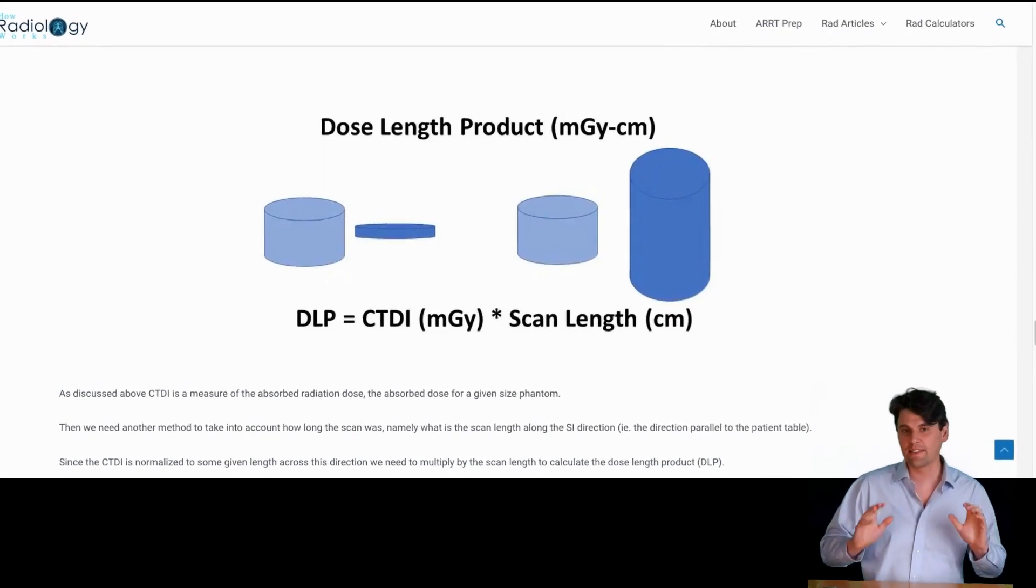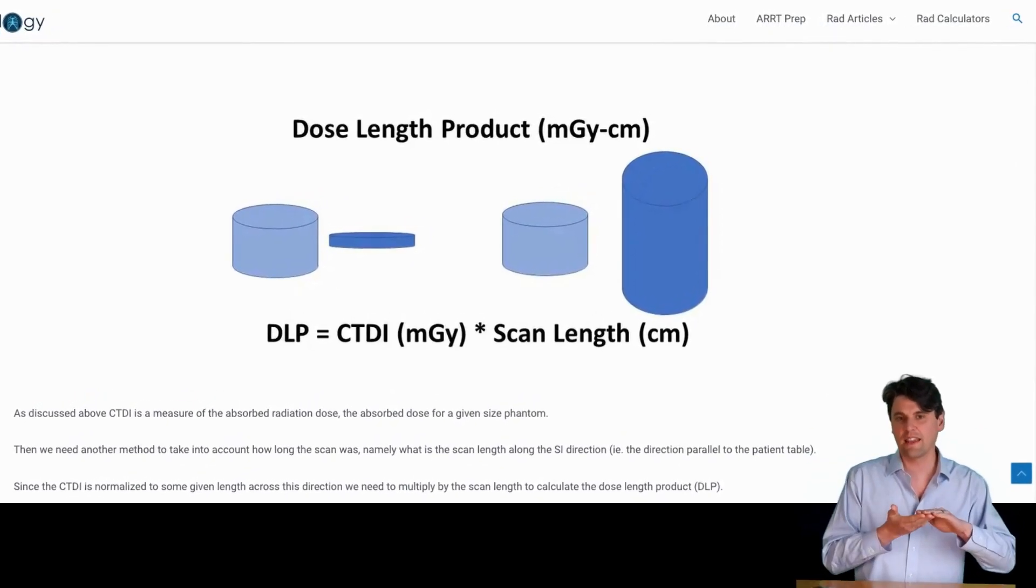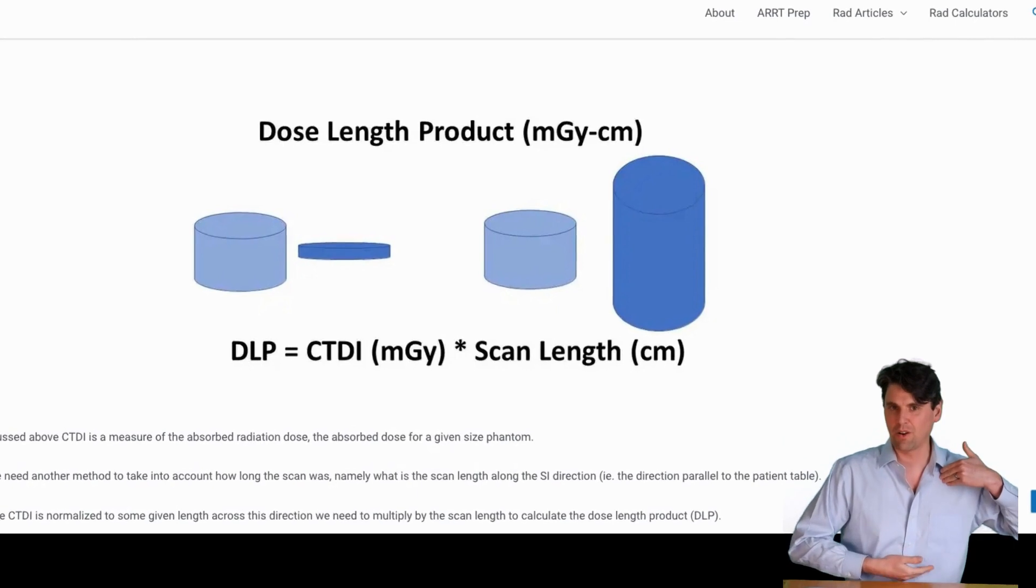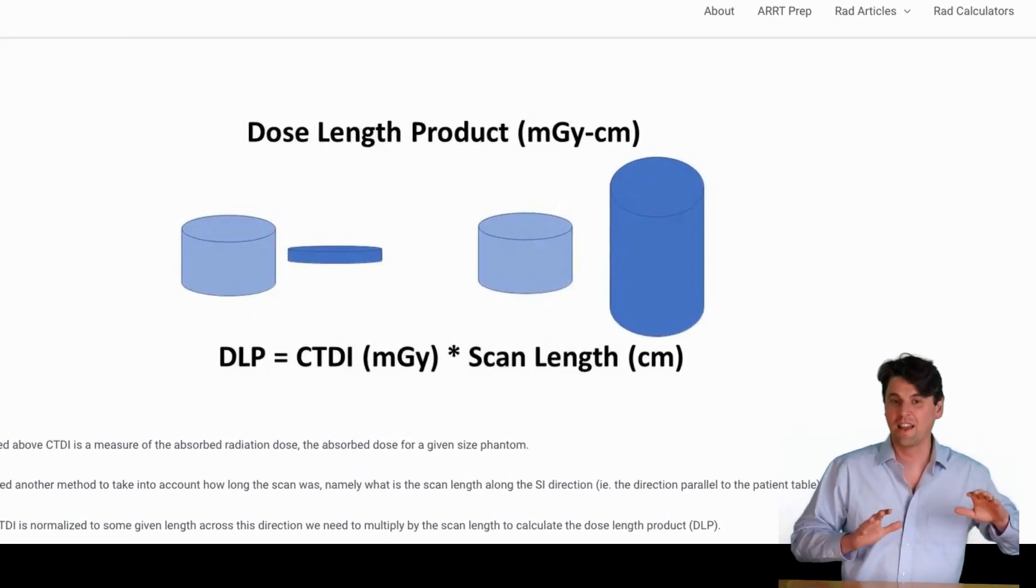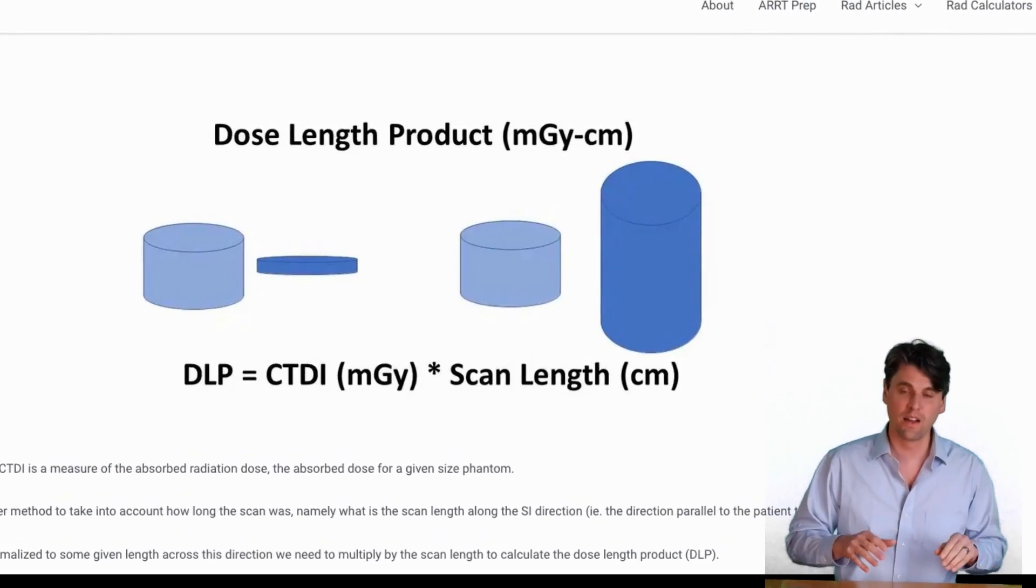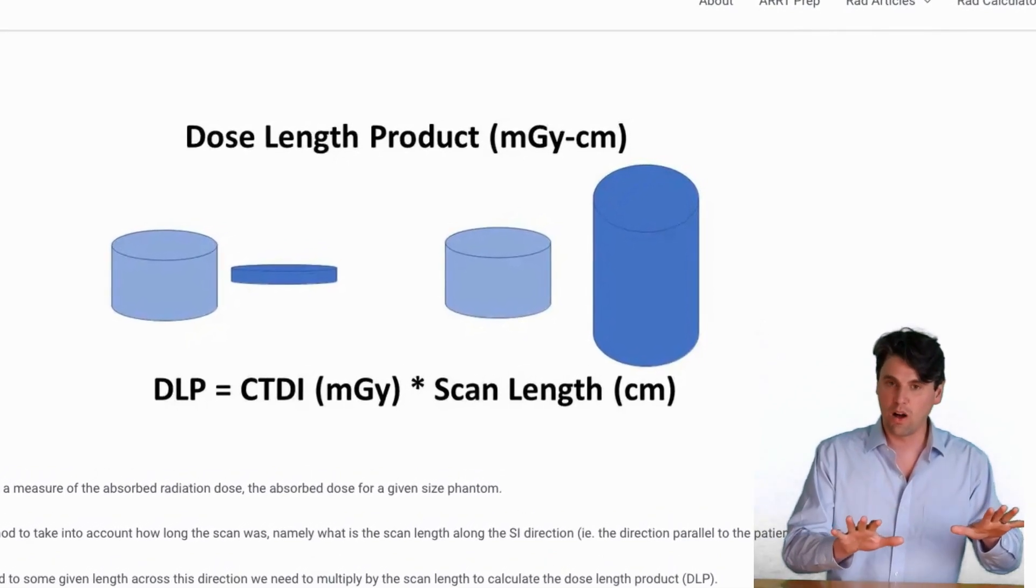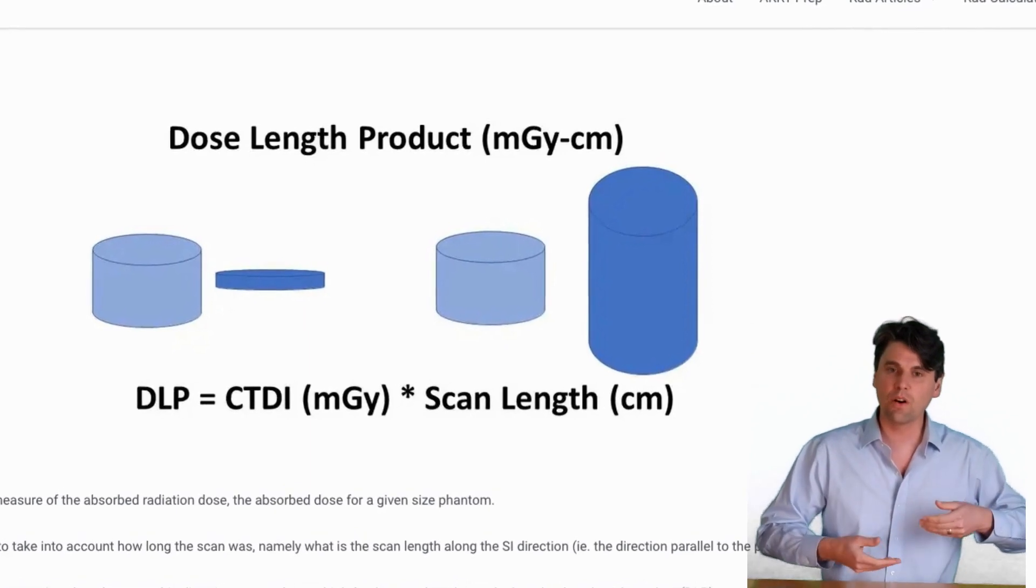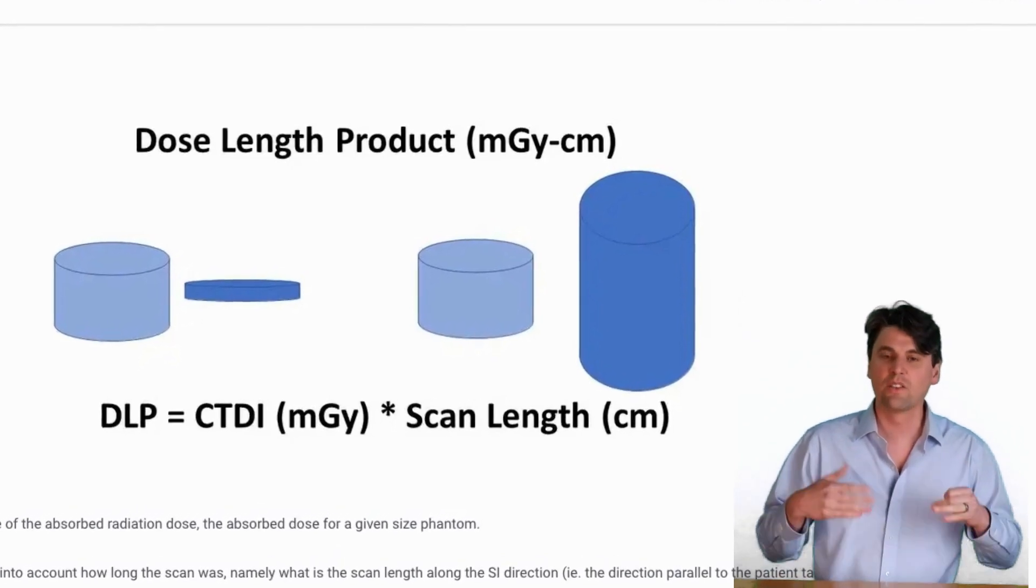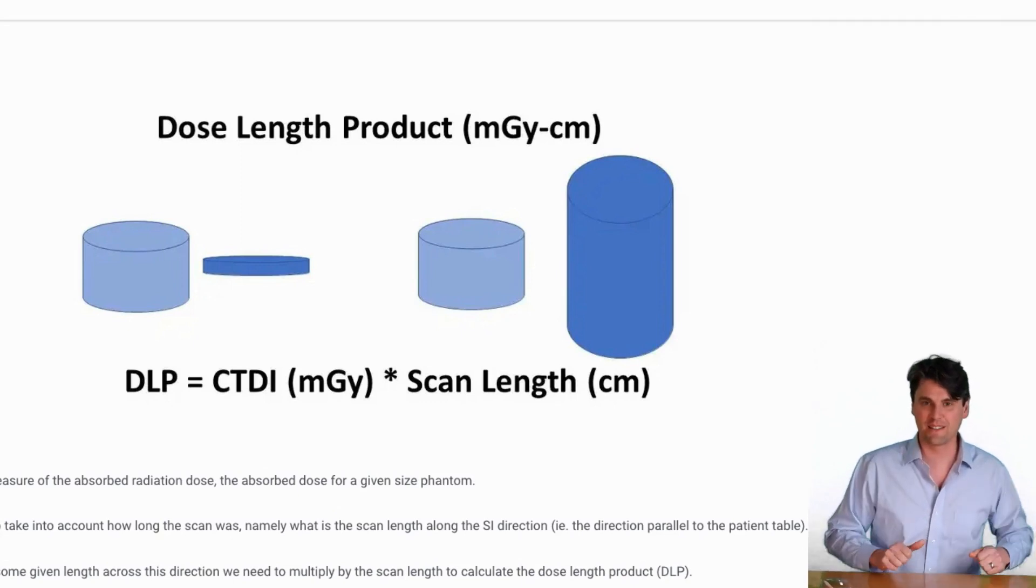We've talked about CTDI so far. CTDI is normalized to a given acquisition and doesn't take into account the length of the acquisition, or the amount of the patient along the Z direction or the superior-inferior direction that was irradiated. For that, we need a new unit, and we call that dose length product. For that, all we do is take the CTDI and multiply by how long of an area was exposed. If we take CTDI by the region that was exposed, that's the dose length product. We'll have units of milligray times centimeters, and we'll indicate the region that was exposed.